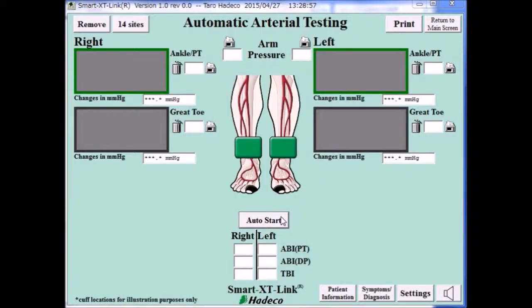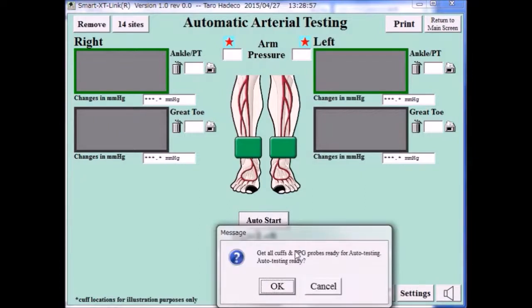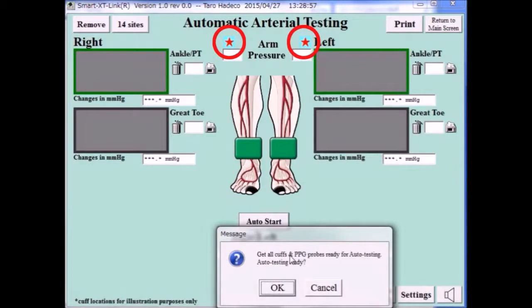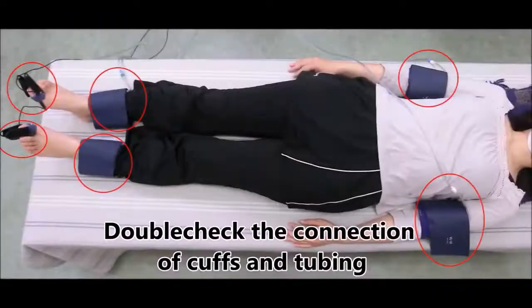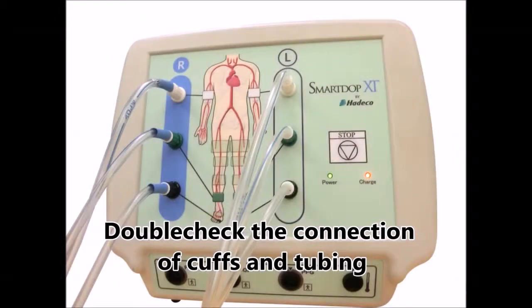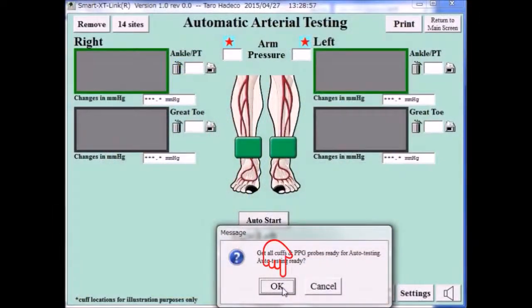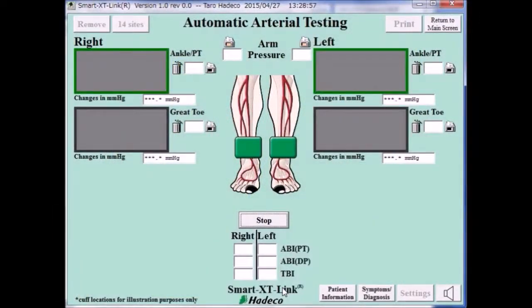Click Auto Start and a message box will appear for checking all the connections. Red star marks represent which sites will be tested next. Once you double check the connections, click OK and the XT will start automatic arterial testing. Now the XT is testing arm pressure on both sides. Pressure is going up.